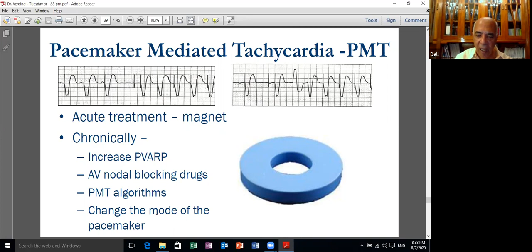You can change the mode of the pacemaker into a VVI, so you avoid sensing the atrial retrograde reactivation. Now, the magnet operation: if you apply the magnet to the pacemaker, it changes into an asynchronous pacemaker. VVI changes into VOO, and the DDD changes into DOO. When the pacemaker lifespan approaches the end, the pacemaker usually changes into a simpler form. You can check that by the magnet early on, and an old way of knowing what remains of the battery is to apply the magnet, and you get the heart rate with the magnet applied on the pacemaker.